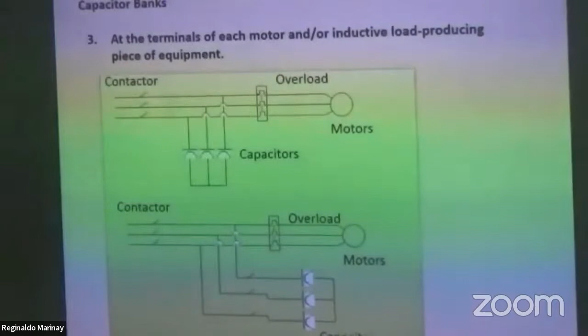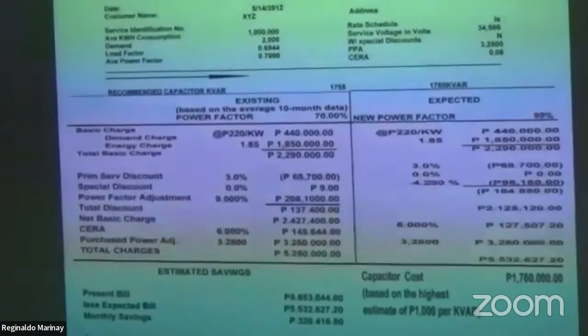And this is the best location, I would say, at the terminals of each load or motor. This is the motor, then there is a capacitor here. There's a capacitor near to the load. That's the best location. Because a capacitor is a loss compensator. It will compensate the loss here in the line. So later I will discuss the loss compensation. Okay, this is the power factor analysis.